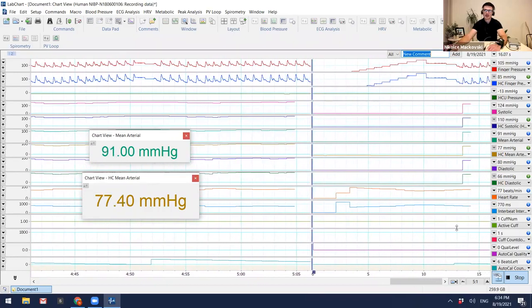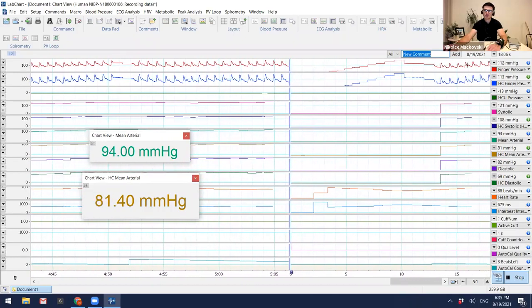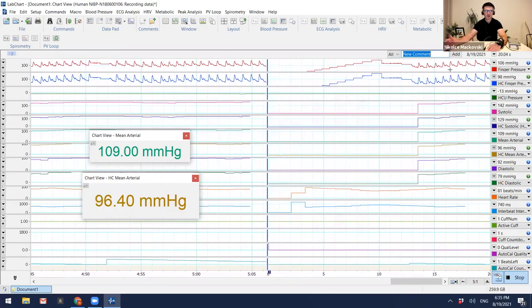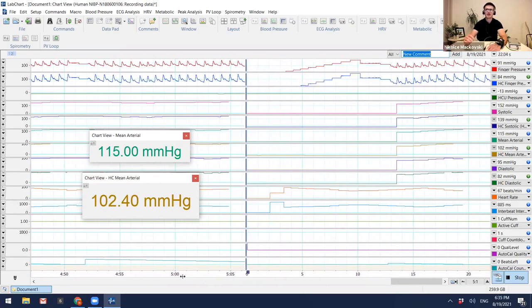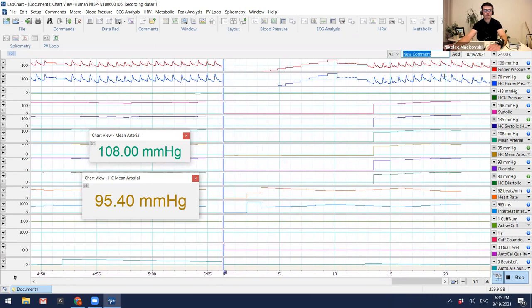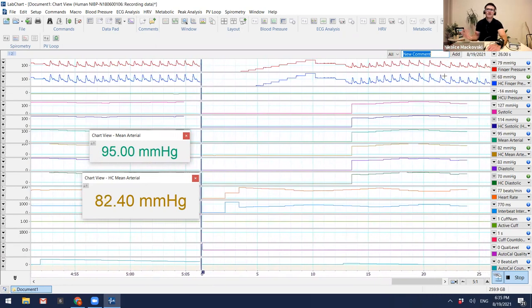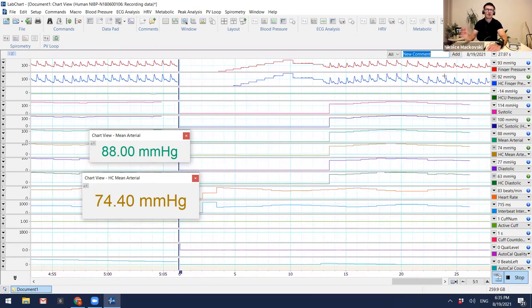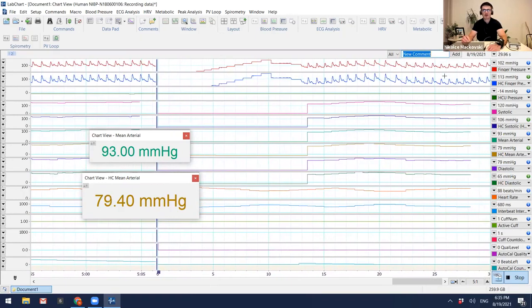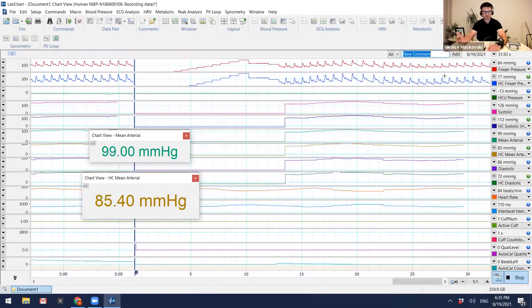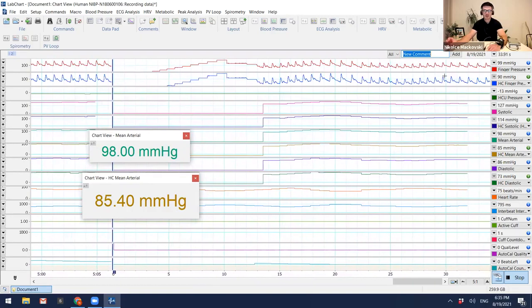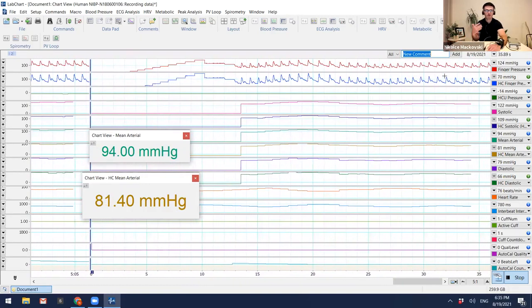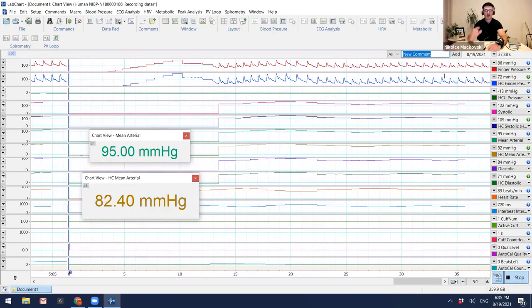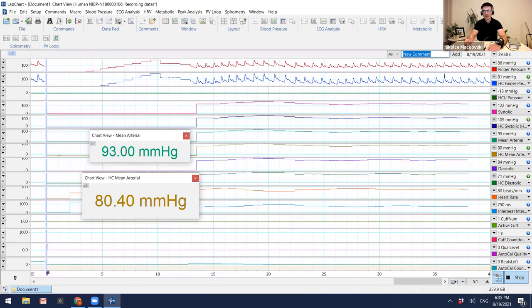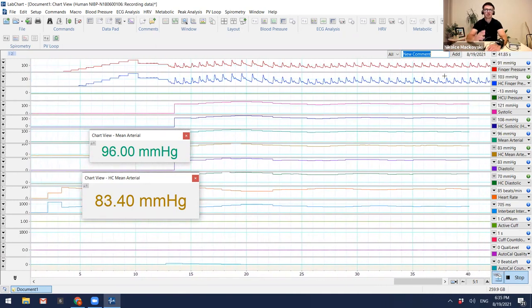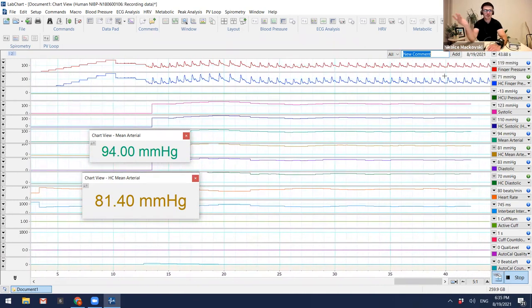So you can see here now that the blood pressure reading, because it's been about 5 minutes, we're getting a pretty good representation of what the cuffs are. If you're doing beat-to-beat heart rate variability and you don't want any disruptions, then I'd recommend recording for 5 to 10 minutes to get the proper set point. And once that's done, you can disable the Autocal and run it continuously.